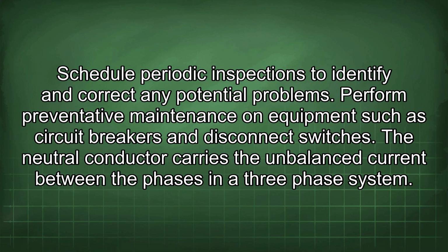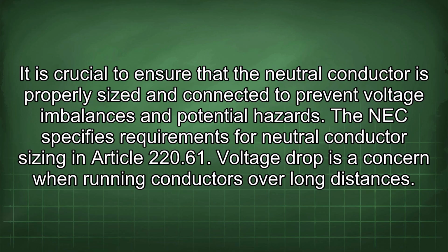The neutral conductor carries the unbalanced current between the phases in a three-phase system. It is crucial to ensure that the neutral conductor is properly sized and connected to prevent voltage imbalances and potential hazards. The NEC specifies requirements for neutral conductor sizing in Article 220.61.